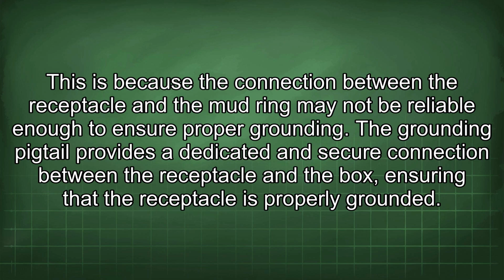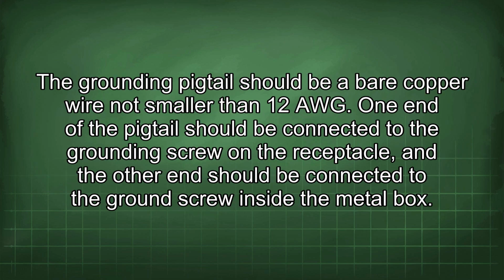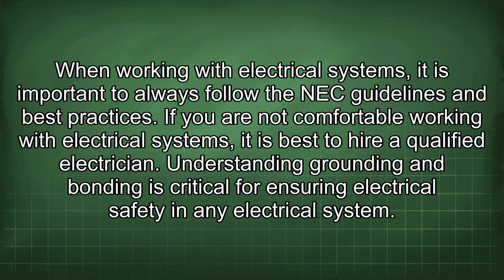The grounding pigtail should be a bare copper wire not smaller than 12 AWG. One end of the pigtail should be connected to the grounding screw on the receptacle, and the other end should be connected to the ground screw inside the metal box. When working with electrical systems, it is important to always follow the NEC guidelines and best practices. If you are not comfortable working with electrical systems, it is best to hire a qualified electrician.